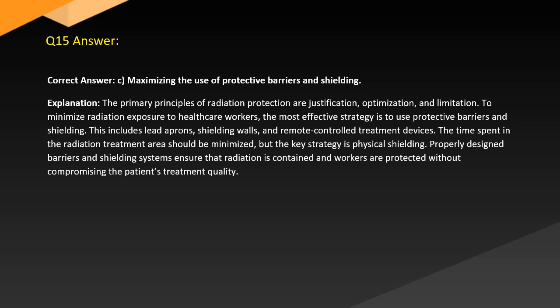The time spent in the radiation treatment area should be minimal, but the key strategy is physical shielding. Properly designed barriers and shielding systems ensure that radiation is contained and workers are protected without compromising the patient's treatment quality.